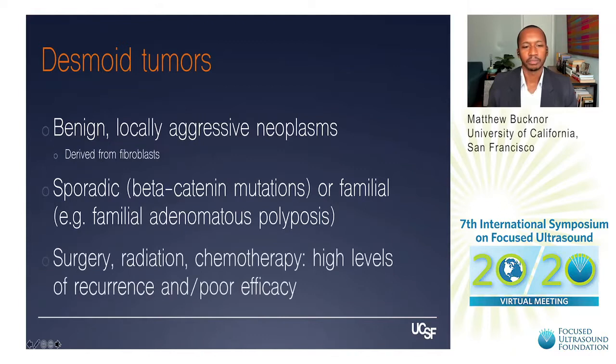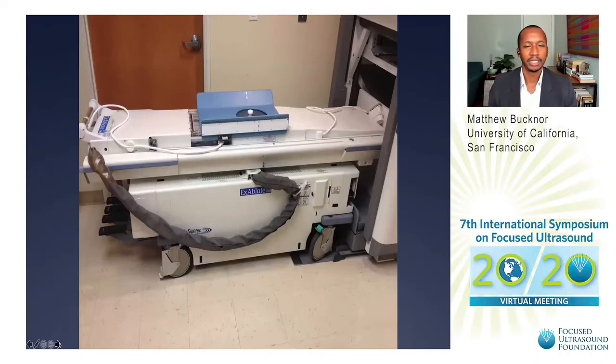Despite many conventional treatments — surgery, radiation, chemotherapy — there tend to be high levels of recurrence. So it's a real opportunity for focused ultrasound to offer benefit for these patients. This is the device used most often to treat patients with these tumors in the United States: the InSightec Exablate device. You can see the large power cord going to the center of the table, with a translucent window supplying the in-table phased-array transducer.